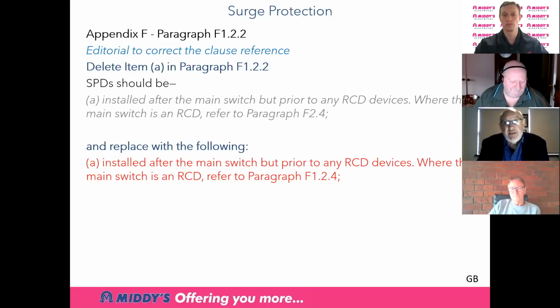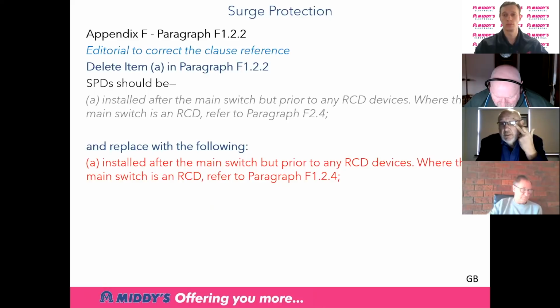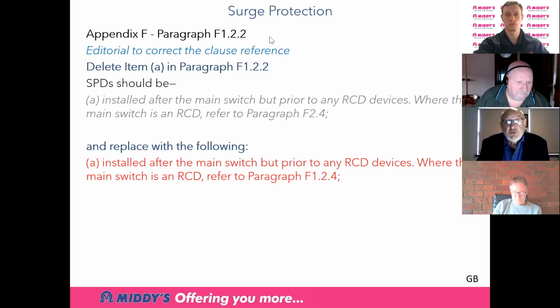Okay, surge protection is Appendix F. Just an informative annex, it gives you some information about surge protection. Basically, we've just had to reword item A under paragraph 1.2.2. So we've taken that grey bit out and replaced it with the fact that an SPD, surge protection device, shall be installed after the main switch, but prior to any RCD devices. Where the main switch is an RCD, then you refer to 1.2.4 within that annex. So there's just some advice to make it a little clearer about putting your surge protection prior to any RCD devices after the main switch.